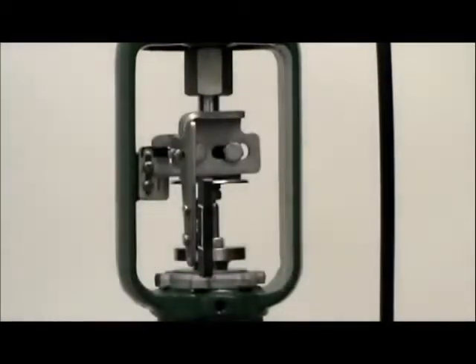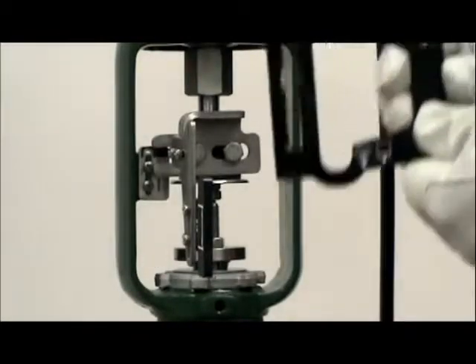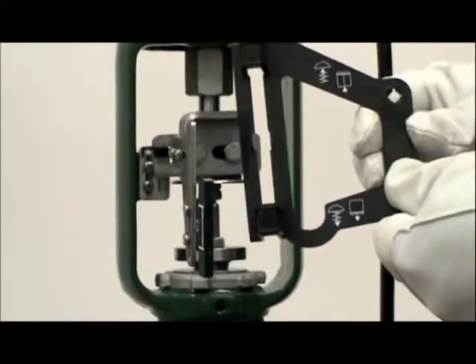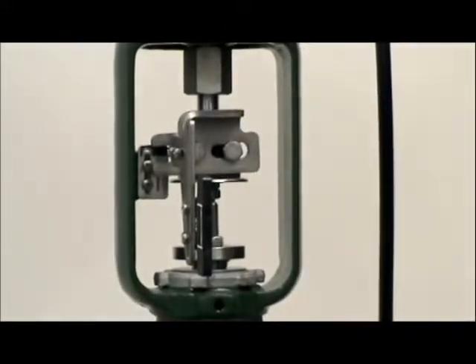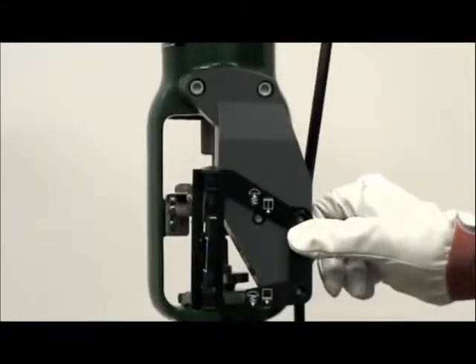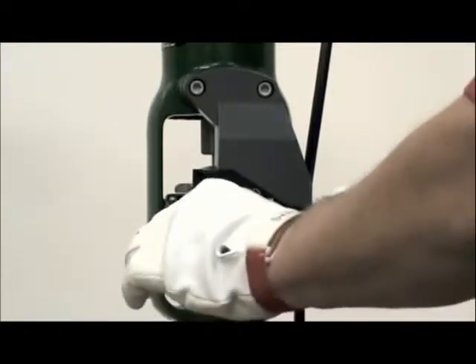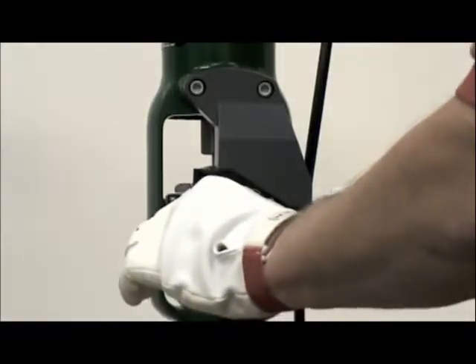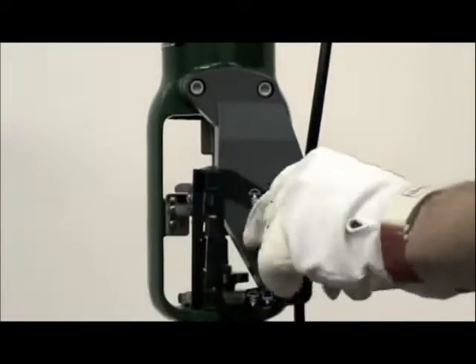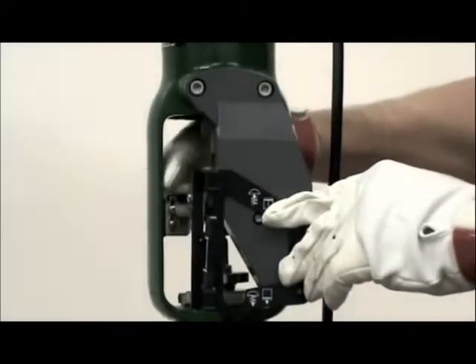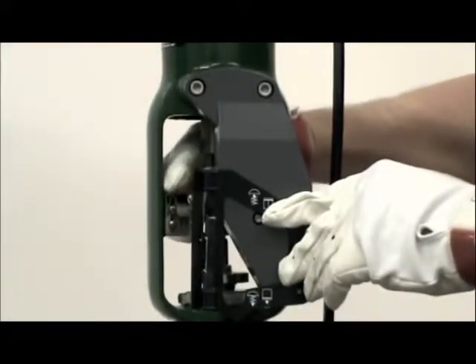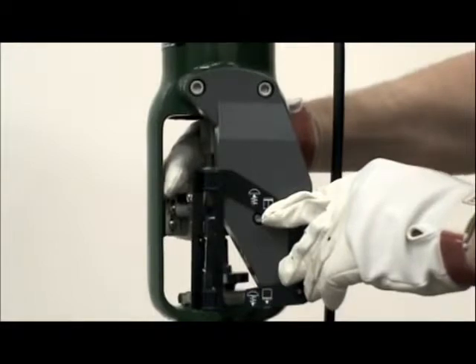Now to find the proper spot for the array, we're going to use our plastic alignment template. The plastic alignment template goes onto the mounting bracket. We've got the mounting bracket attached. Next, install the template on the mounting bracket and verify that we have the array in the proper location for its side to side adjustment. This looks pretty good.